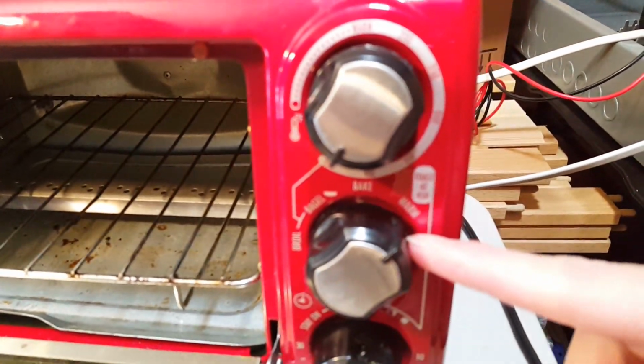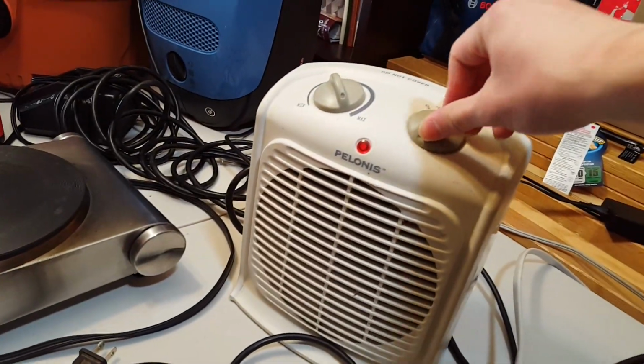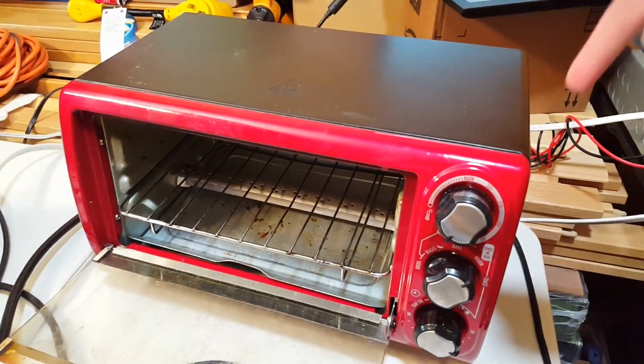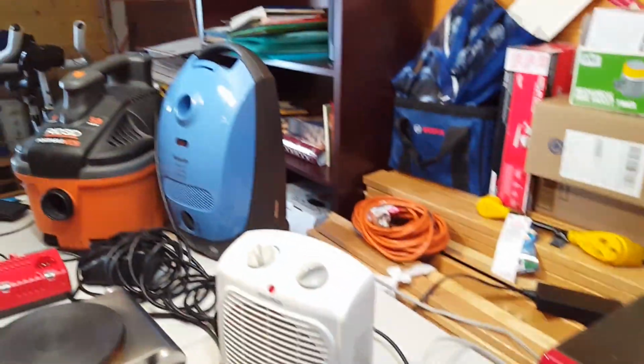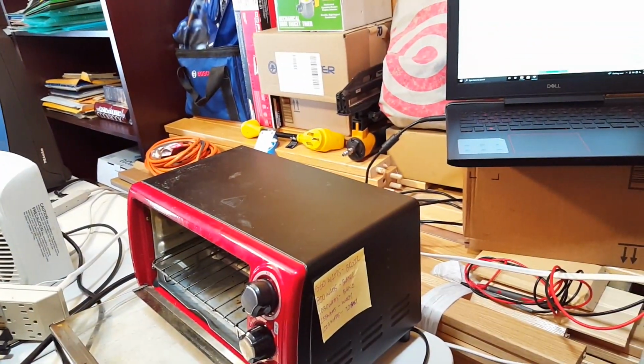This right here is on the warm setting. This is on the highest setting, which is 1500. 250, 1750 plus the shop vac. It just failed. The BMS is in error mode. It went to overcurrent. This is, oh my goodness, this is just no good.